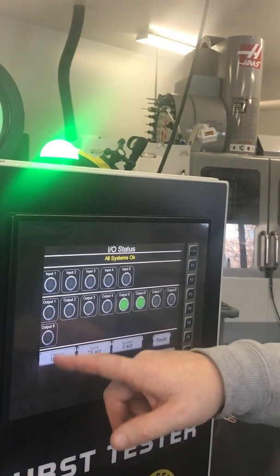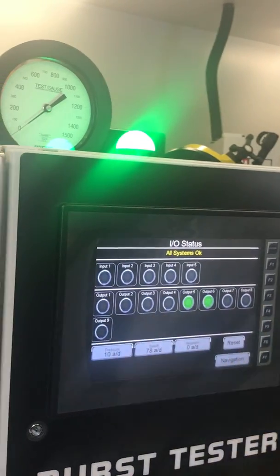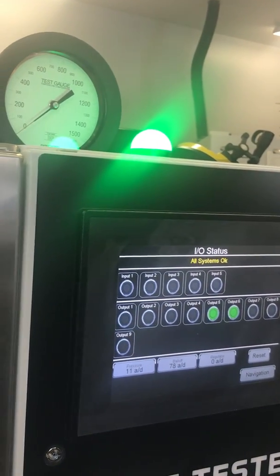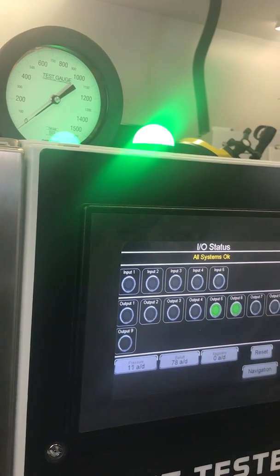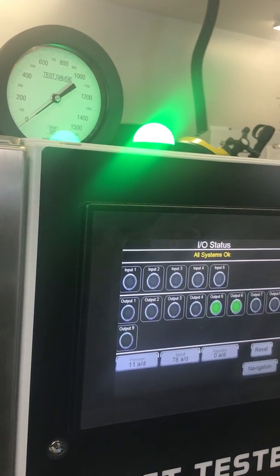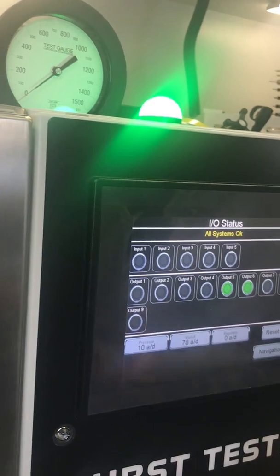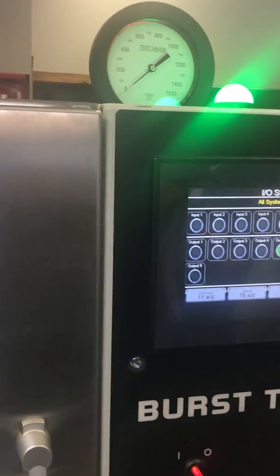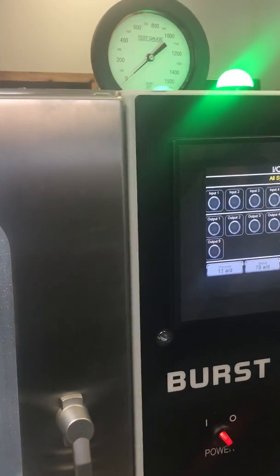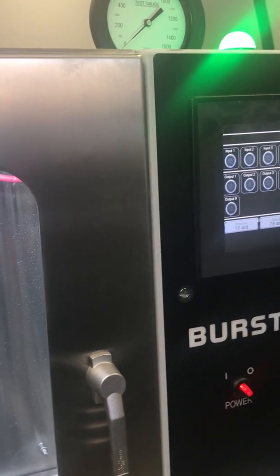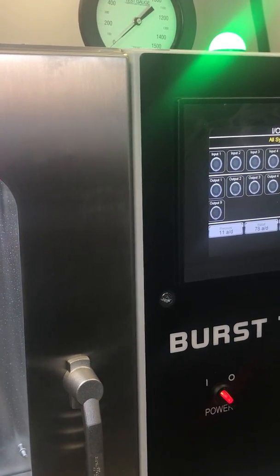And here we can kind of see our A to D is coming in, analog digital conversion. That's a raw number. It's usually 0 to 32,000. Okay. So everybody says it's 4 to 20 milliamps. Well, the PLCs don't read that. You get a number. Red lamp is 7 and 8 is yellow lamp.